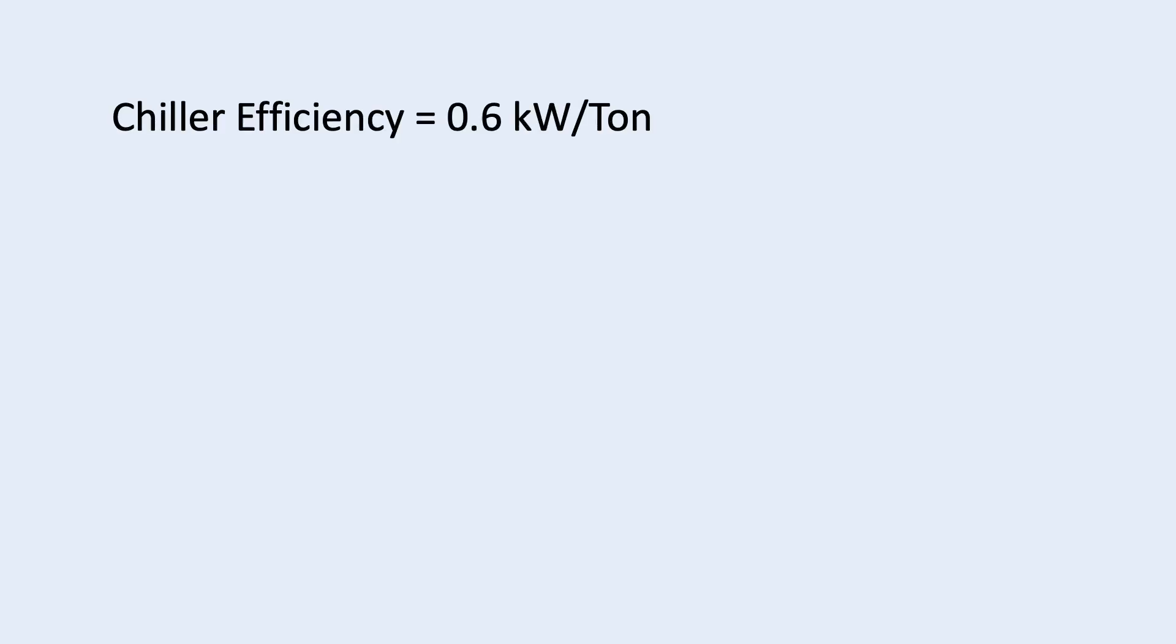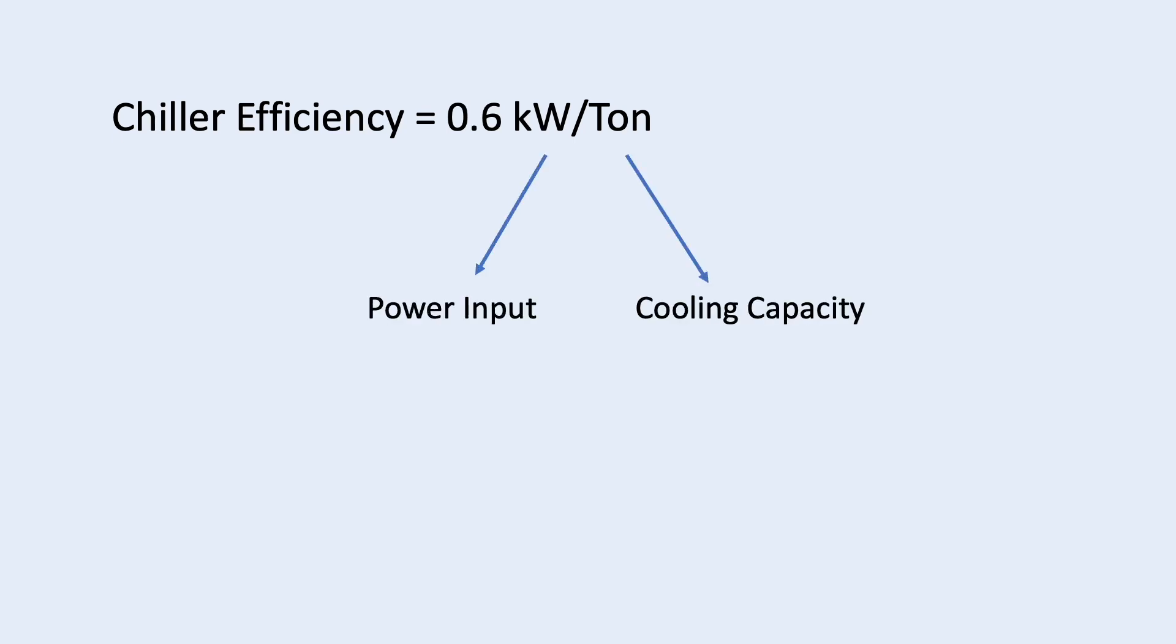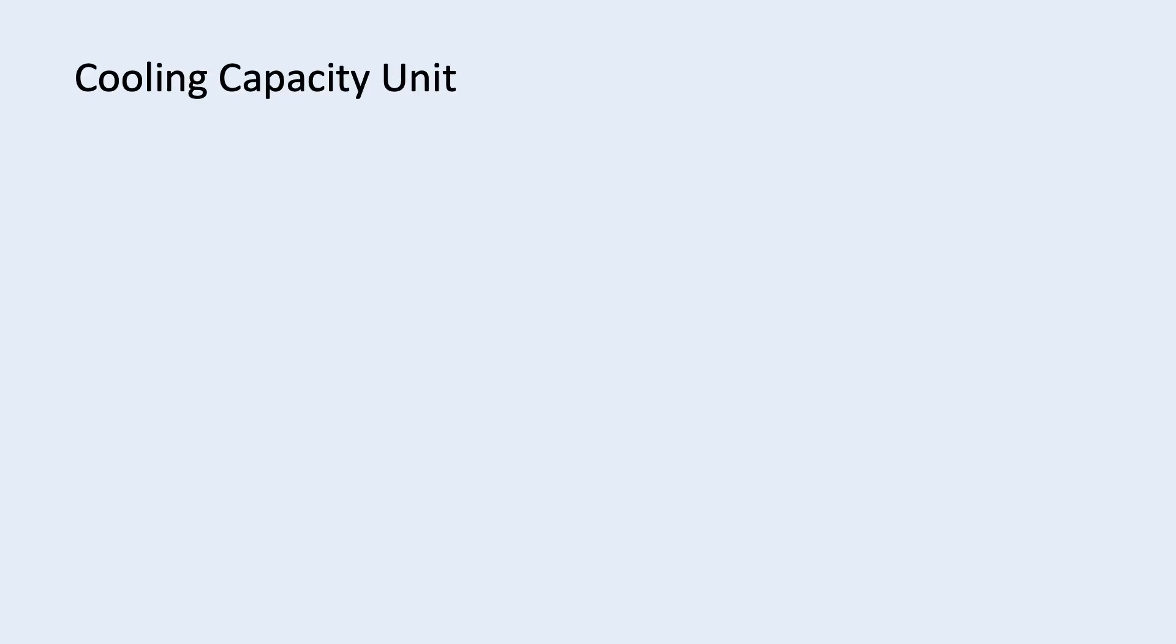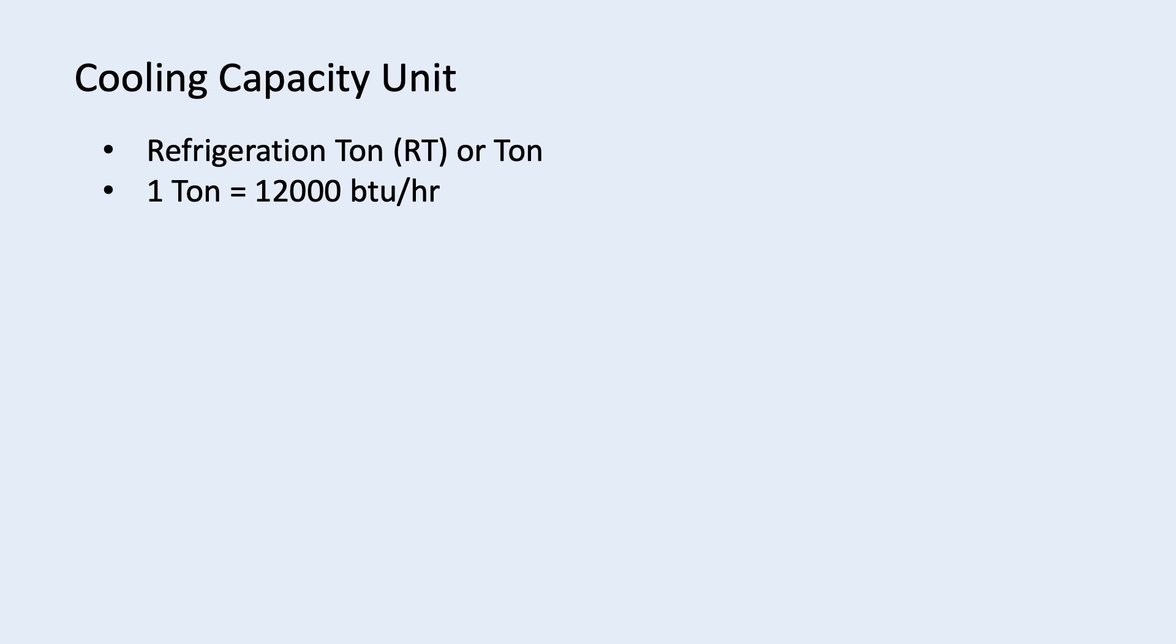Earlier, we used 0.6 kilowatt per ton as the efficiency of the chiller. Kilowatt is the power input and ton is the cooling capacity. So, kilowatt per ton is power input divided by cooling capacity. The unit for power input is always kilowatt. But the unit for cooling capacity can be ton, kilowatt and BTU per hour. For cooling capacity, we normally use ton for chiller. Then, 1 ton is equivalent to 12,000 BTU per hour and 1 kilowatt is equivalent to 3412 BTU per hour.